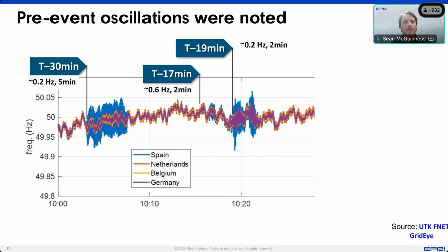Then 17 minutes prior to the event, a second smaller oscillation began to occur. The oscillation frequency was about 0.6 hertz, with relatively small magnitude, and that persisted for just 2 minutes before damping out.